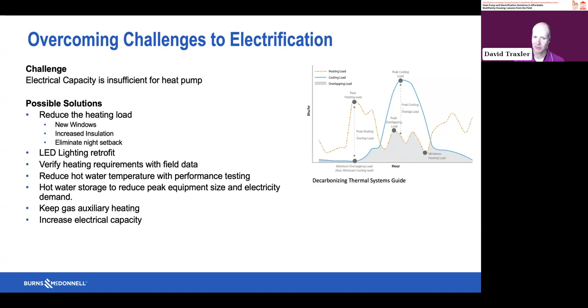Marie talked about manual J calculations, which contractors use to determine heating and cooling loads of the building. Those loads are good, but if you can verify the actual loads in the field, that's even better, because then you get a clear idea of how much heating and cooling are actually needed, and you can appropriately size the equipment, which makes a big difference.